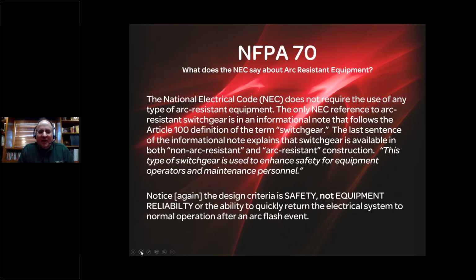With respect to the National Electrical Code, I want to be clear, the code does not require arc-resistant equipment. The only reference in the entire NEC is in Article 100, where it defines what switchgear is. The last sentence is just an informational note, and it says both non-arc-resistant and arc-resistant construction is available. And it says that this type of switchgear is used to enhance safety for equipment operators and maintenance personnel. But again, consistent definition here, even within NFPA 70, the National Electrical Code, the design criteria is on safety, not equipment reliability or the ability to return the electrical system to normal operation after an arc flash event.